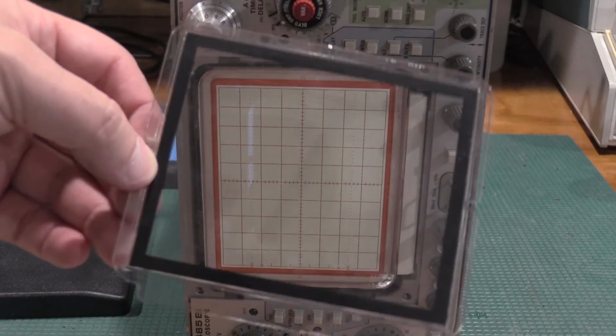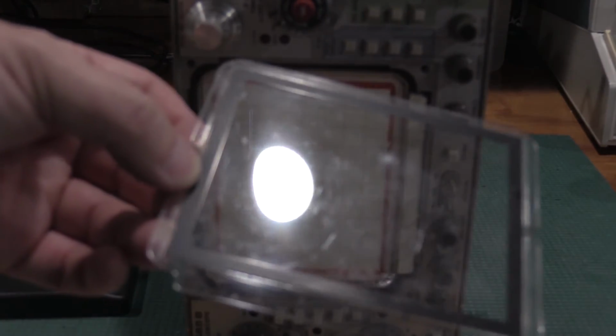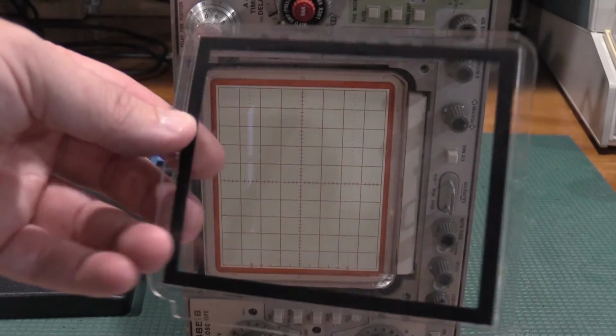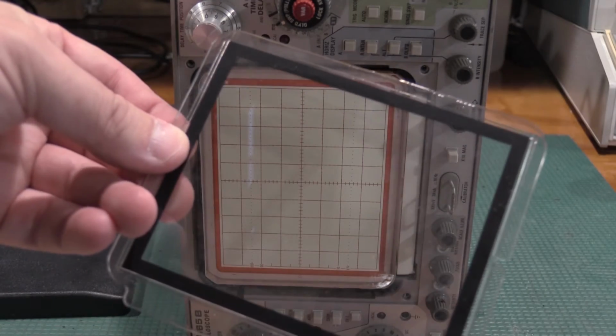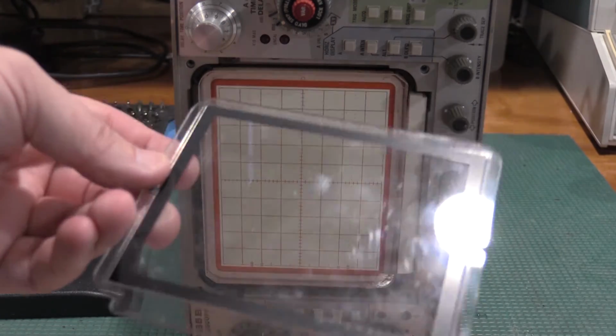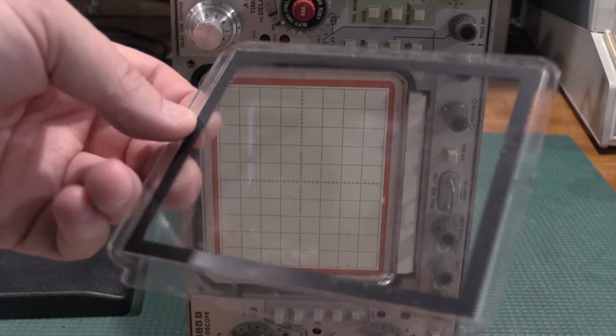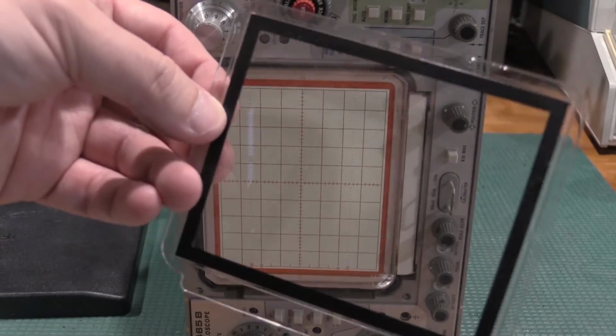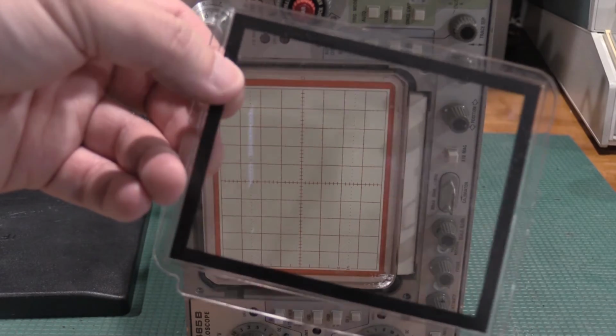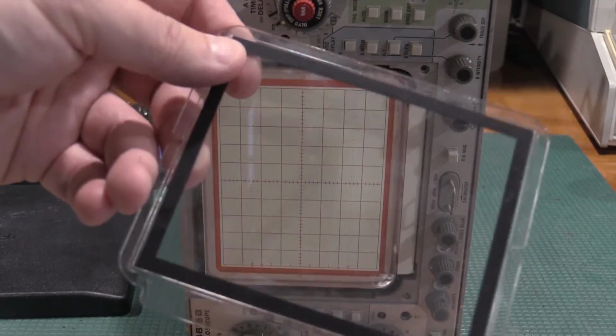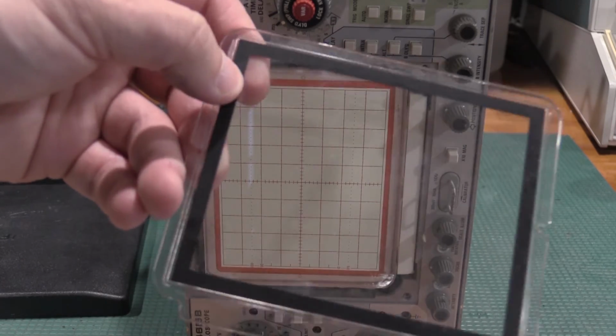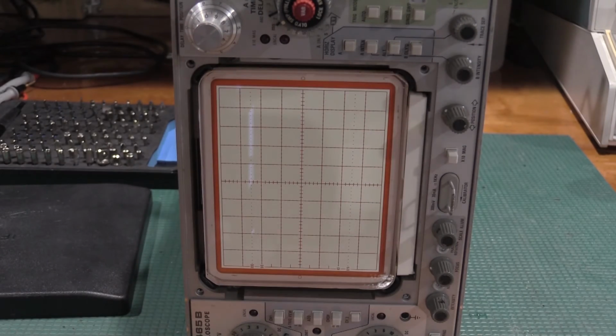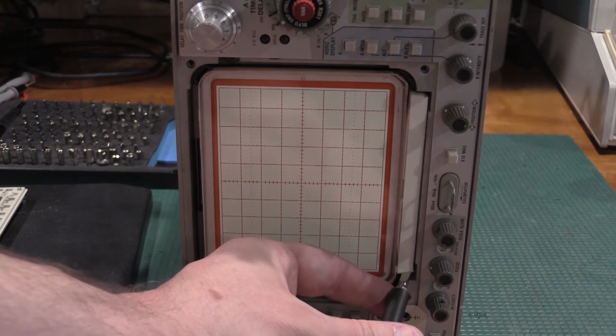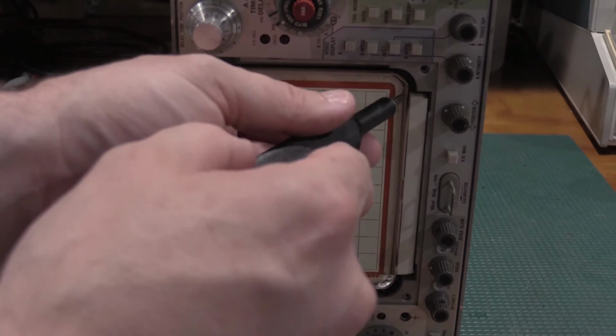There aren't any deep scratches in this, so everything looks pretty good. It's got the typical plastic scratches, so I'm not going to need to resurface this. If I was going to need to resurface this, I'd use emery paper on it, take it up through the grades. If anybody's interested in seeing that procedure, let me know. I will see if I can find an example of a screen that needs it. This has a black tape on it as a light dampener, so I want to be careful that I don't actually rub that off when I'm polishing the front of this piece of plastic, but I'll hit it with a buff wheel just to clean it up a little bit. The lamps on here are underneath this plastic.